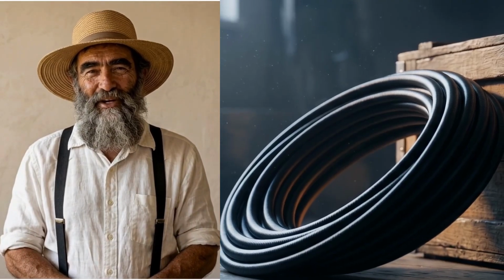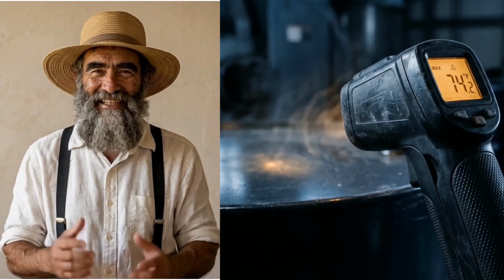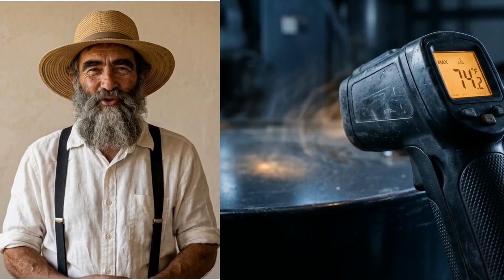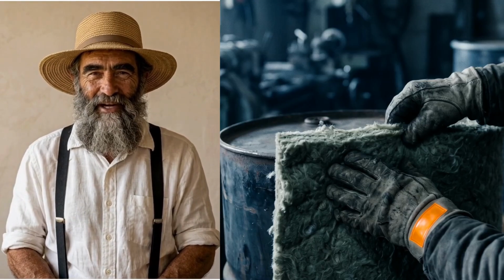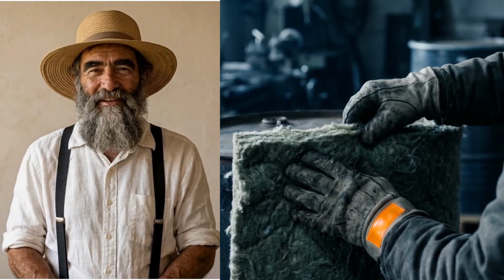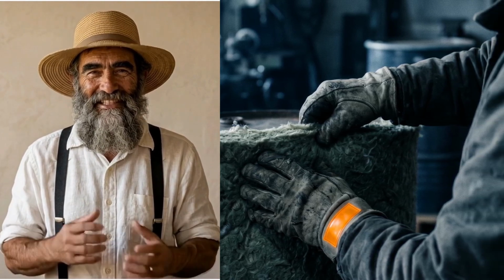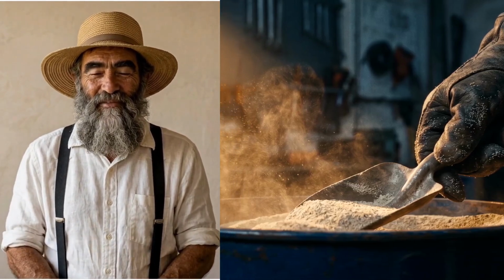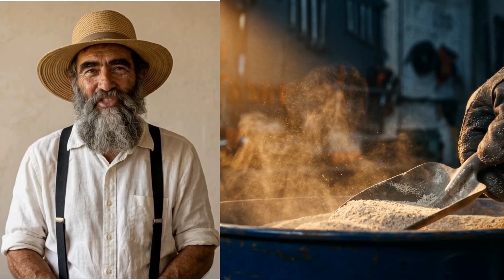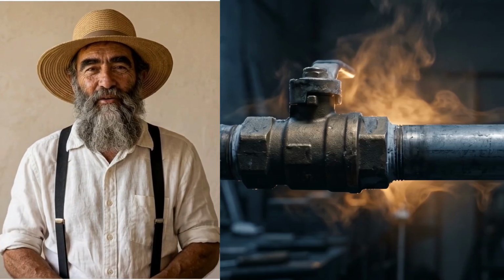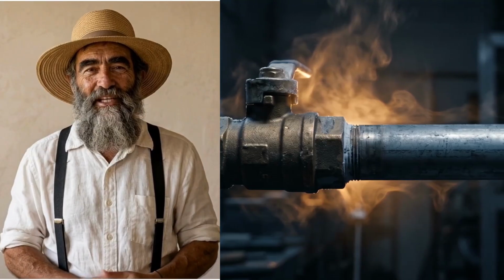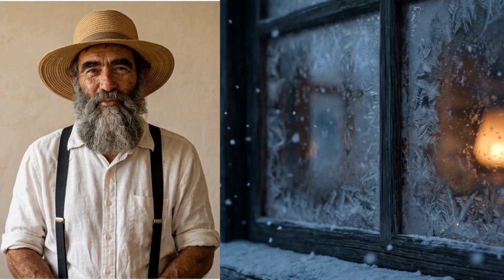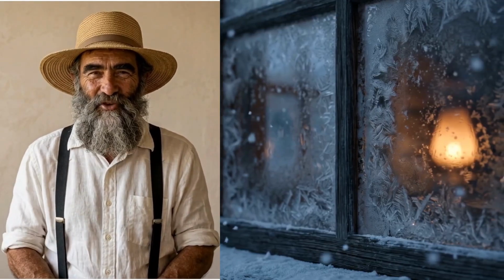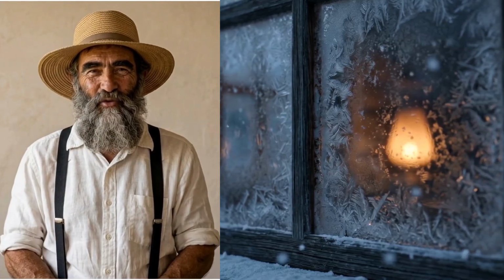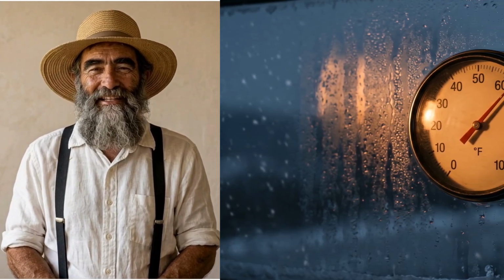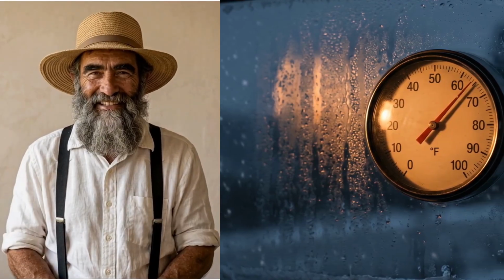Total material cost breakdown. 200 feet HDPE pipe, $200. 12-volt DC fan, $15. Pipe fittings and manifold box, $40. Intake vent screen, $12. Miscellaneous hardware, $20. Total $287. Add the cost of your labor digging the trench, or hire a local excavator with a trencher for $300 to $500. Total project cost $400 to $900, depending on whether you dig by hand or hire equipment. Build time: 1 weekend to dig and lay pipe, 1 day to connect and test.